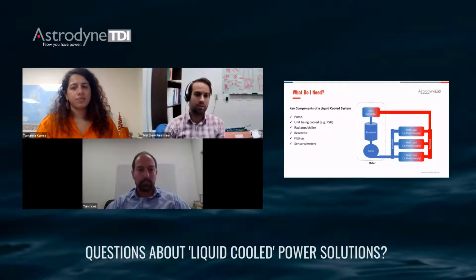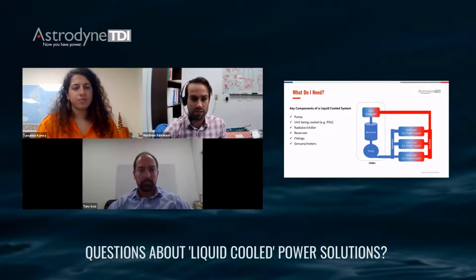The main components of a liquid cooled system are the reservoir, which needs to be properly sized to provide enough coolant to the entire flow volume of the system; any hoses or piping which deliver coolant to and from the power supply; and fittings used to make connections. Fittings are highly customized and cover a broad spectrum of types, sizes, and features such as valves. Also pictured here is a manifold, if you're going to connect more than one unit in the same system in parallel, and then eventually a heat exchanger, which removes the wasted heat from the coolant. Then there's the pump, which needs to be sized to overcome any pressure drop introduced by the components making up the coolant system.